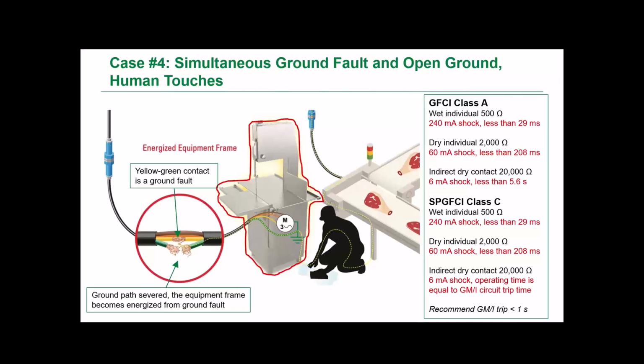However, at that 20,000 ohm level, there is a difference. So at the 20K value, that fault will create about a 6 milliamp current that would be going through the person, which would cause a mild shock. Now this is detected by the Class A GFCI and will trip in less than 5.6 seconds. Now, in the case of the special purpose GFCI, the Class C, it has a trip level of 20 milliamps, so it would not respond to the 6 milliamp fault current. However, that ground monitor interrupter feature that we've been talking about would be detecting that severed ground, and that will cause the device to trip.